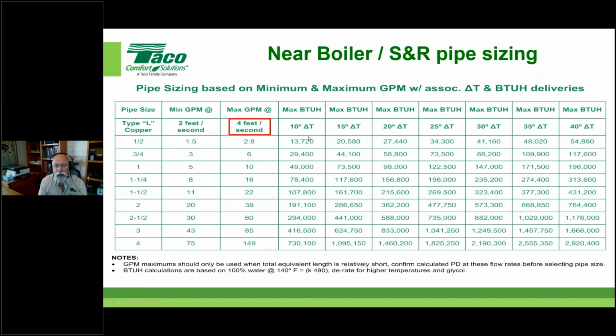And this is just showing you at a given delta T, what could you transfer at this maximum. For instance, if I had a 1-inch pipe and I ran 10 gallons a minute through it at a 20-degree delta T, what should that be? Right around 100,000 BTUs, and it is. So just understand that. But let's say that we went out to a 40 on a condensing boiler. I could do 200,000 BTUs.